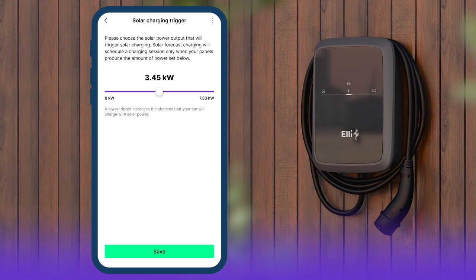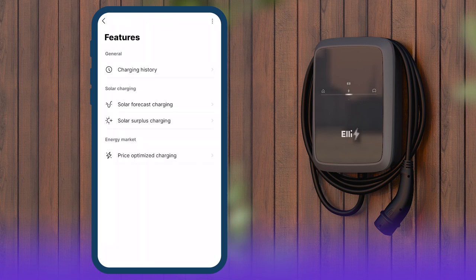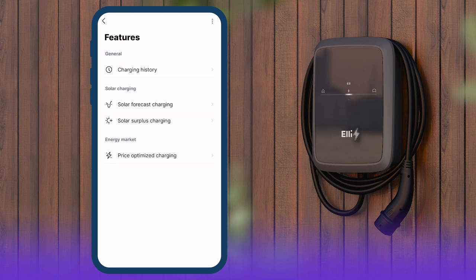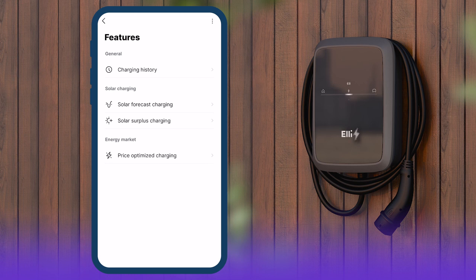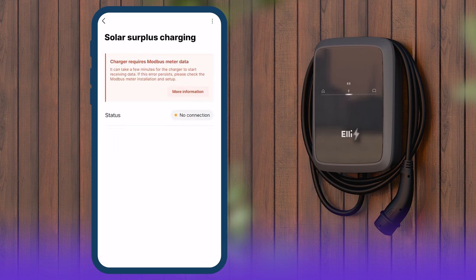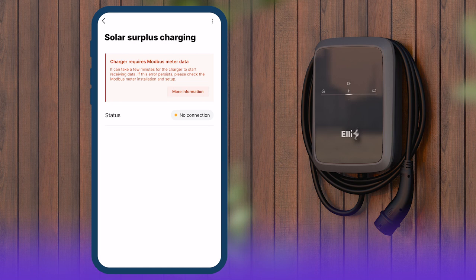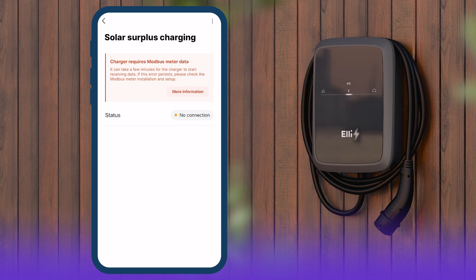Elli Chargers connected to an external Modbus electricity meter can be set to charge only when the solar panels produce more energy than the household consumes. Tap on Solar surplus charging on the home screen to set up the function. If no Modbus electricity meter is connected or installed, this will be displayed in the next step. The connection can be carried out by a certified electrician as part of the hardware setup.